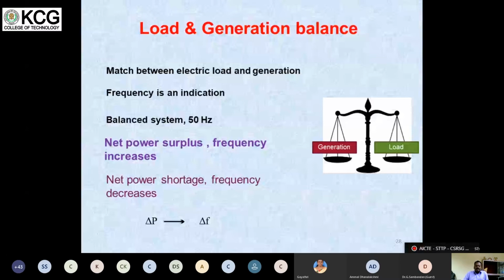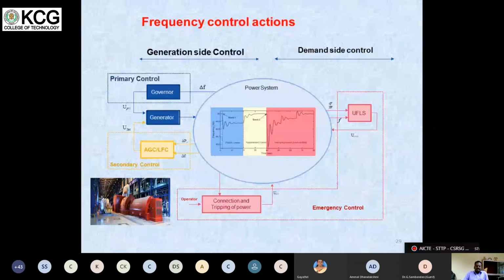And frequency control, as we have discussed already, can be done on the generator side using the prime mover, and on the demand side using low frequency relays. Normally we use low frequency relays on the demand side. If the frequency goes down, that means the load is more and generation is less. So if we curtail some of the load in the system, the frequency can be maintained.